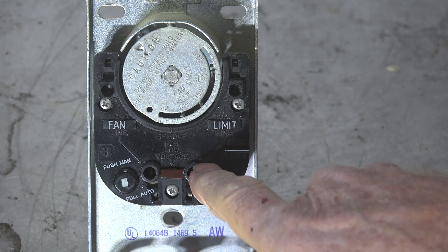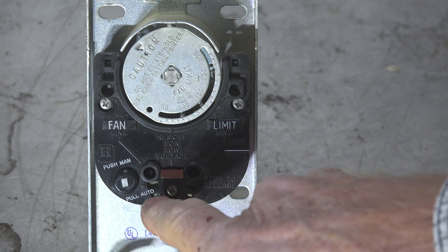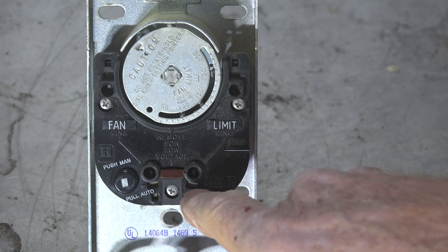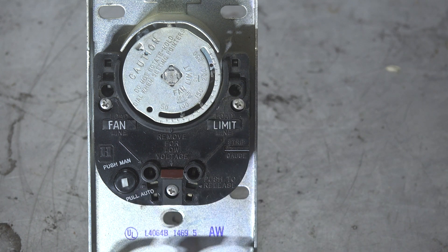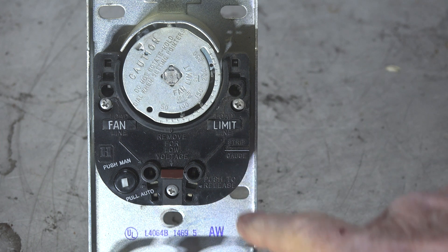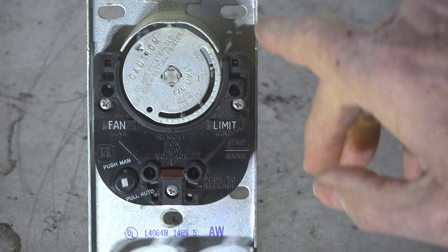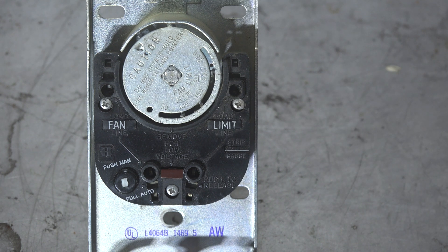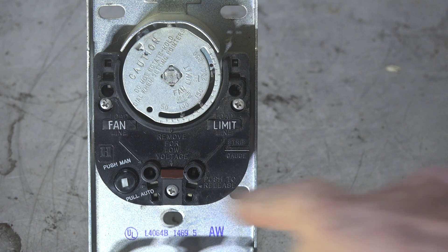In very old furnaces, the way these things used to work is we would feed power in here to the bottom, and there's a jumper between the two—and I'm going to explain that in a minute—so that there would be power on either side. If the limit shut off, it would shut off the 120 volts to the control system of the furnace.